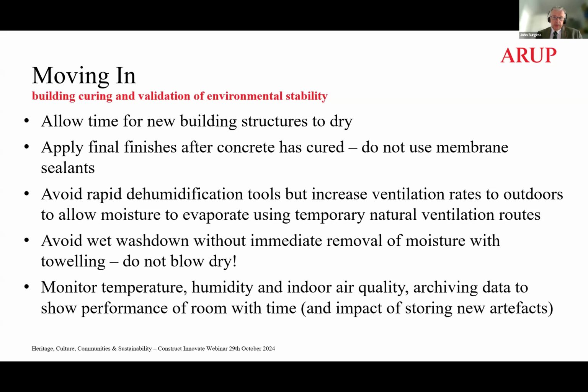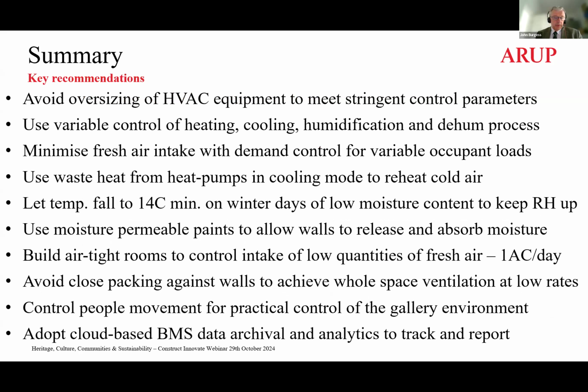And then monitor the temperature, humidity, and indoor air quality using an archival system coupled with the building management system to prove how the building is working and learn from its shape, its design, and the systems that are operating in there. Avoid oversizing of HVAC equipment. So much is unnecessarily spent for buildings that don't need it. Minimize fresh air intake, so use indoor air quality sensors. Use waste heat from heat pumps in cooling mode to reheat cold air. Use the wider bands suggested by the Bizot group. And use moisture permeable paints on the internal surfaces.